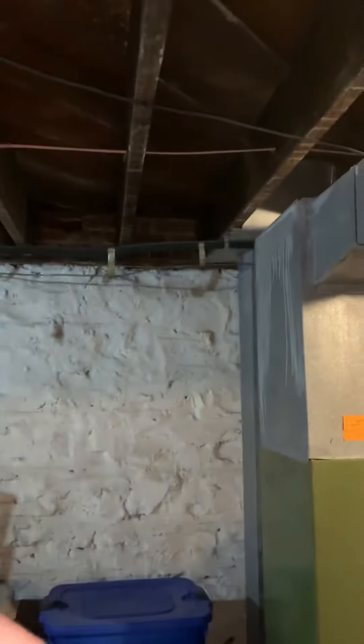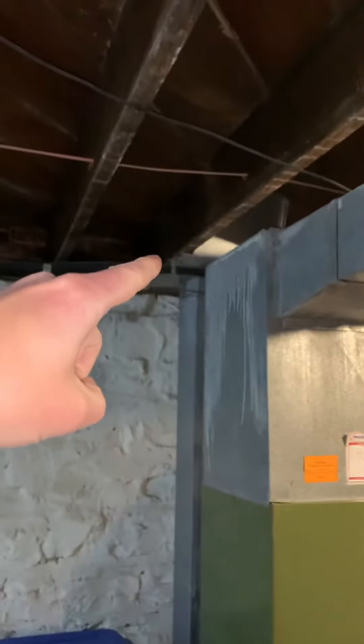They do have a concern with airflow noise. Currently they've got a common floor return up on the main floor. We're going to try to reduce the noise and velocity going through there, so I'm recommending we put some ductwork in.